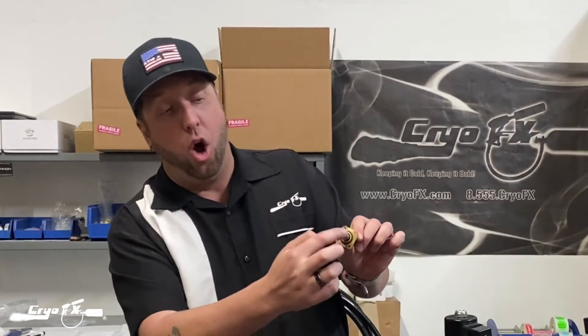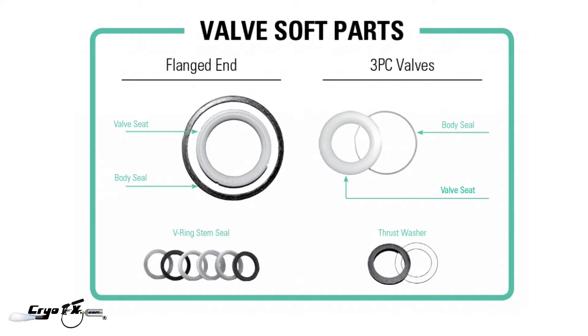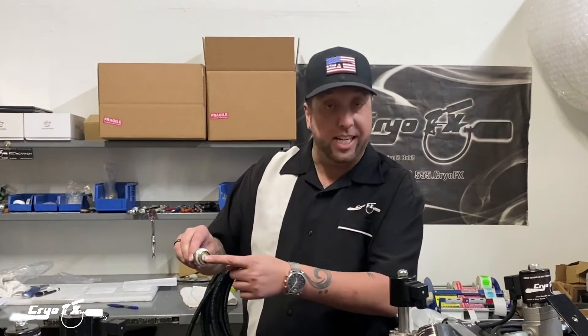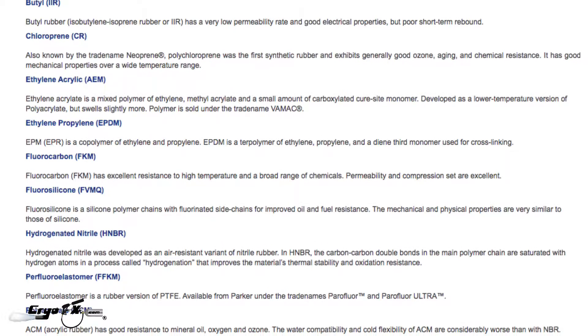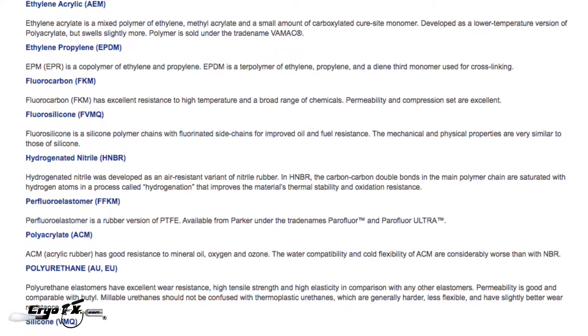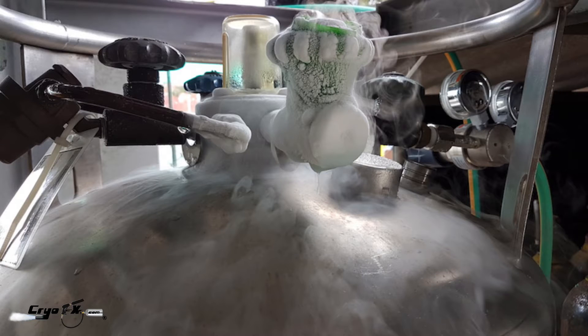The seats and seals inside the valve are going to cause you problems if they're wrong. Inside the valve you have little O-rings and different seals — a seal on the outside and another on the inside. The material matters: you have PTFE, Teflon, and a number of different variants. If you get the wrong type, the valve gets super cold — liquid CO2 valves can get down to negative 40 degrees — and you're going to end up with a CO2 valve leak.